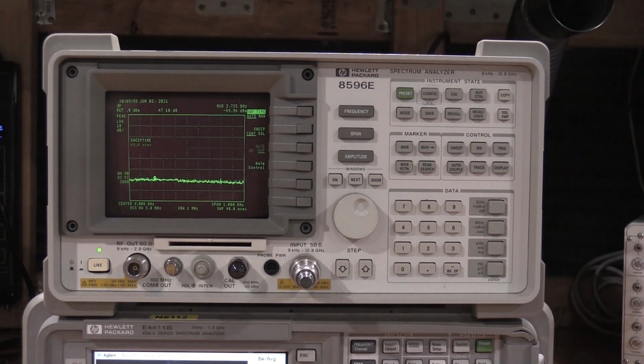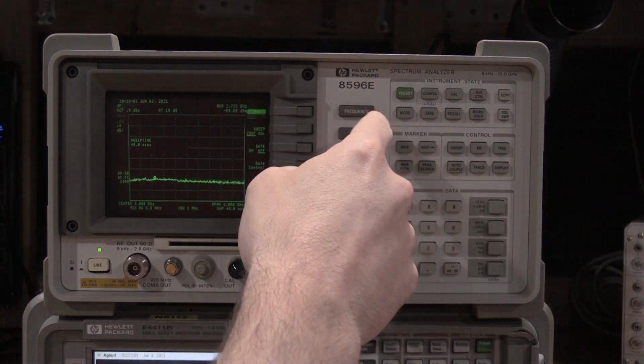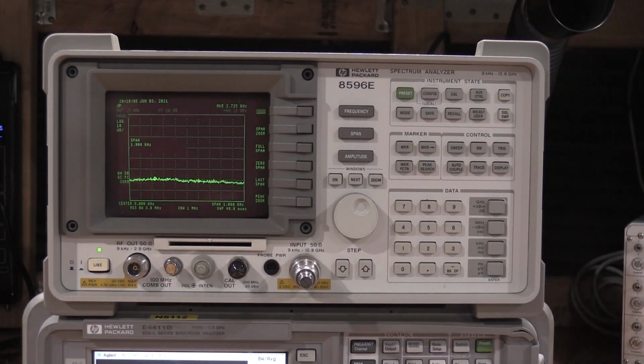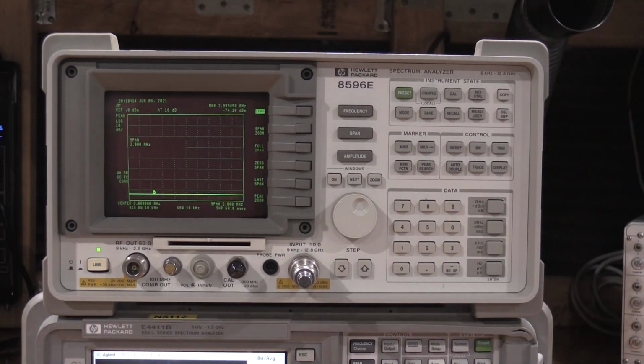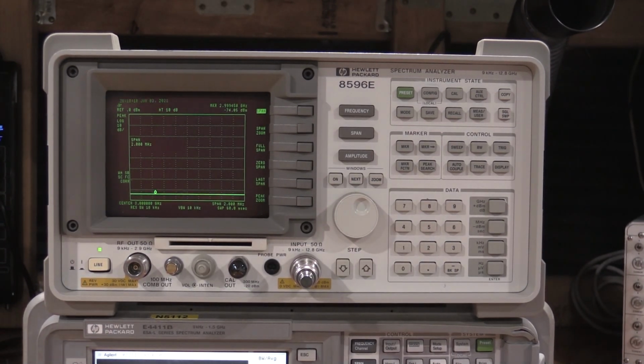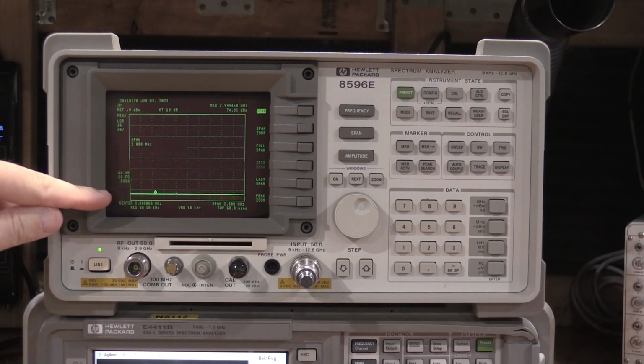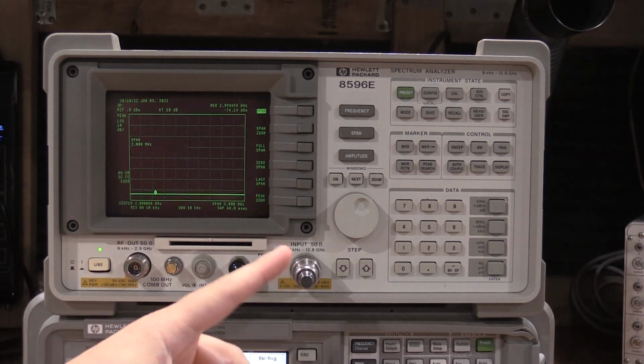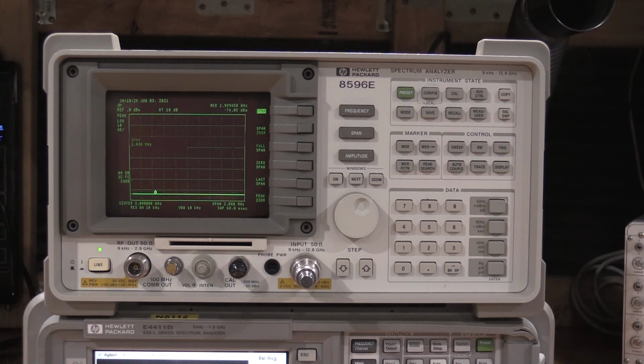And it's using a resolution bandwidth of 3 megahertz. But if we drop the span to 2 megahertz, we have a nice flat line. So it's just a nature of the beast with the sweep speed. So this is perfect. This is what I'd like to see, especially with a 50 ohm terminator on there. So that is wonderful. Everything is good.